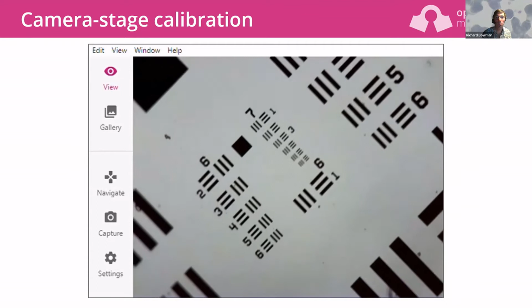We can even model things like the mechanical backlash of the stage, but I probably shouldn't bore you with the mathematical details there. What I can say is that if you want to move the microscope around a predefined path, then this closed loop move enables you to make a much more accurate move. So the error without that closed loop correction is probably a few microns per move. After you've done the correction, you can get it down to a couple of 100 nanometers if you're very careful.